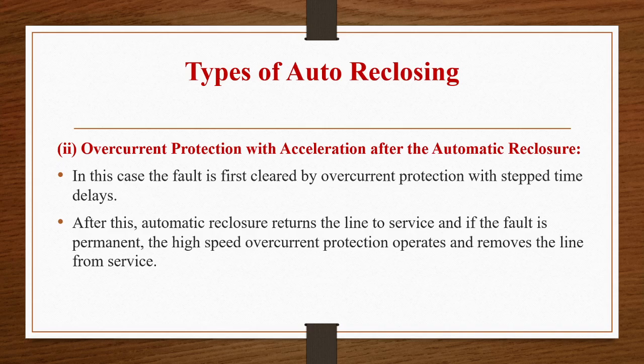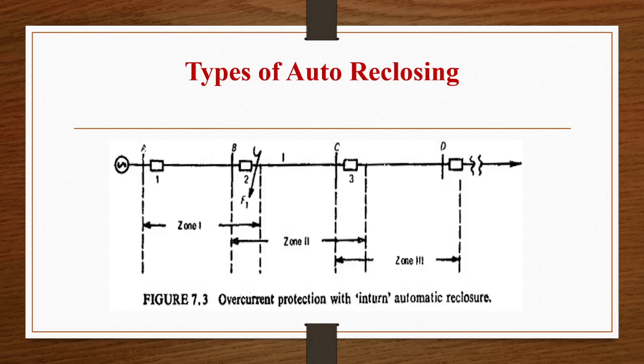In this case, the fault is first cleared by overcurrent protection with stepped time delays. Then after this, automatic reclosure returns the line to service, and if the fault is permanent, high speed overcurrent protection will operate and will remove the line from the service. So what is happening in this case? The fault is first cleared by overcurrent protection with step time delays, and after this automatic reclosure will return the line to service, and if the fault is permanent, high speed overcurrent protection will operate and remove the line from the service.